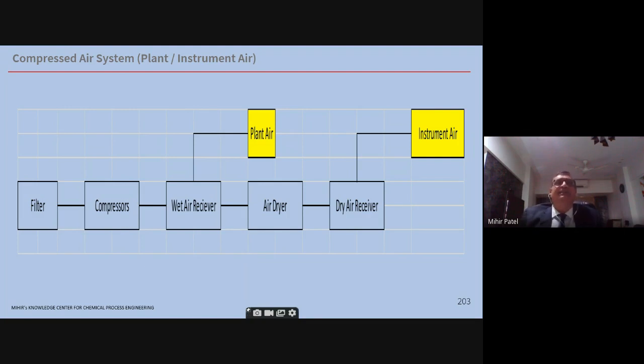Then dry air receiver is there. This is very important. You have to store 15 minutes of dry air. It is not mandatory, but it is good engineering practice. And for the minimum dry air pressure, there's an alarm at the outlet of the dry air receiver, which gives a low pressure alarm at 4 bar. That 4 bar is minimum required because the actuator requires minimum 4 bar gauge. So if normal instrument air is being produced at 6 bar, then between 6 and 4, the dry air receiver has to store 15 minutes of consumption. Okay, that is a very good engineering practice.